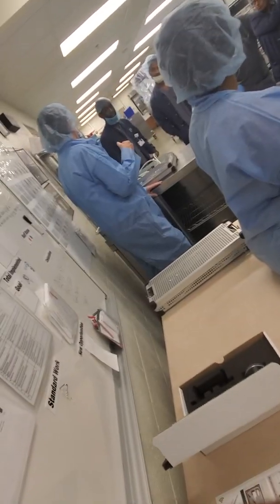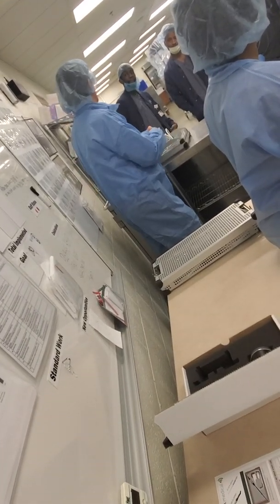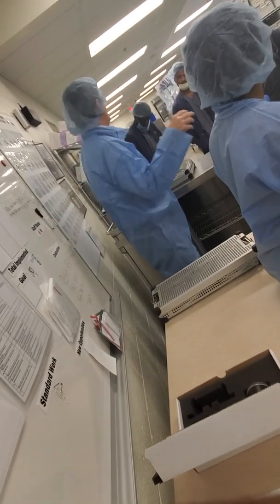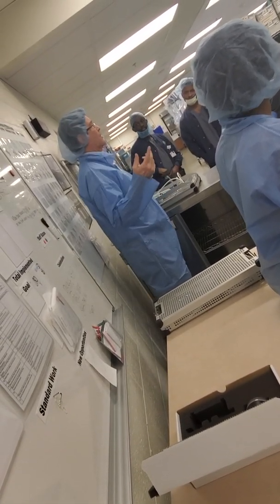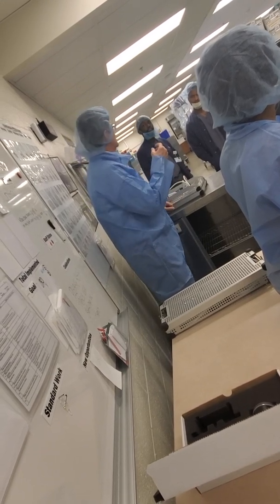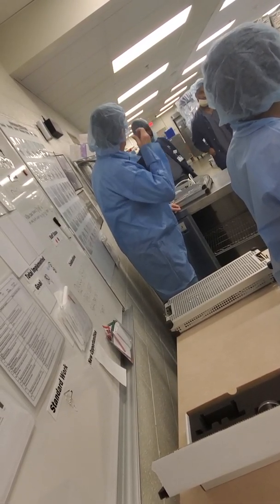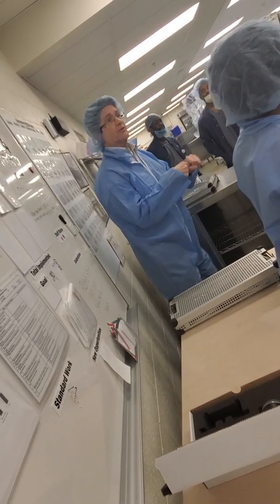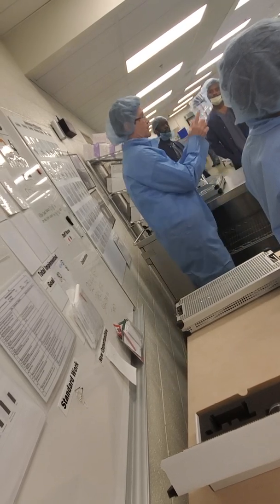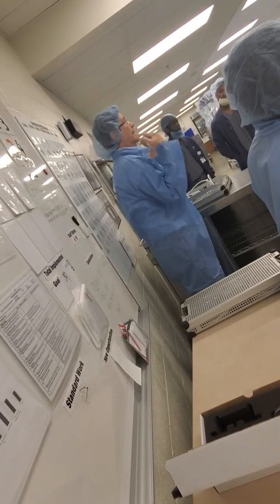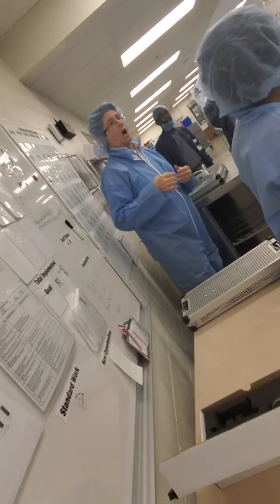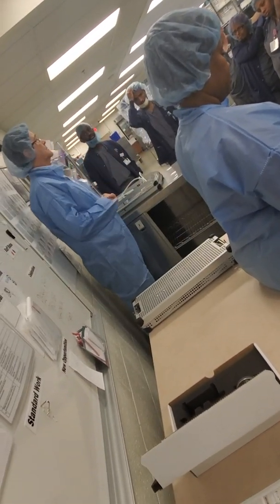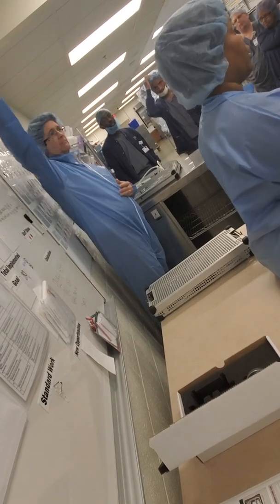I got a good story for you, real quick. Had a customer, wait a minute. They put their probe in water. Well, there was a little port in it. Well, they put a cleaning thing in it. I told them not to. They had that probe for like 2 or 3 years. All of a sudden, it said something's wrong. So I went there to go visit. And I picked up the probe and it had water inside. Because they put a brush inside. And there's a little tiny piece of tubing that they disconnected and water got in when they cleaned it. Okay? So I'm just saying that stuff happens, but you gotta do as best you can to avoid damaging the probe. Okay? Just one more thing I wanted to add.